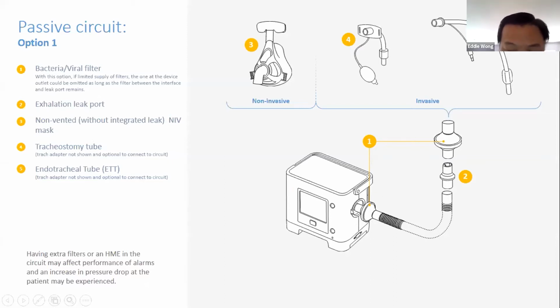It's very important you put the bacterial filter at the ventilator port before you attach the patient tubing, because you do not want the bacteria exposed to the room air, or whoever visits the patient, handles or changes the tubing, or does suctioning, causing the bacteria or virus to go back to the machine and infect the patient. So a bacterial filter is a must when you use a ventilator in the hospital. Some home patients I visited do not apply the bacterial filter at home, because some doctors tell them home is safe compared to the hospital.